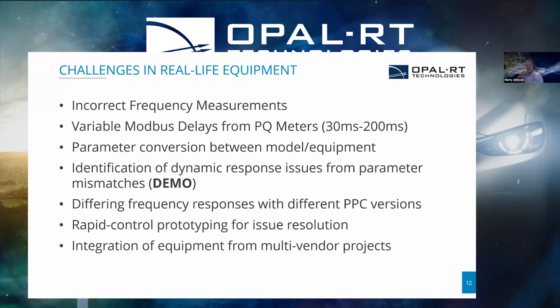With this kind of distribution, you see a bell curve of these delays. Sometimes you can't really capture what's going to happen when events occur at that 200 milliseconds, even if it's operating as per your model. For example, in some controllers, if their cycle time is lower than that 200 milliseconds, all of a sudden you miss a cycle, which can lead to large instability.